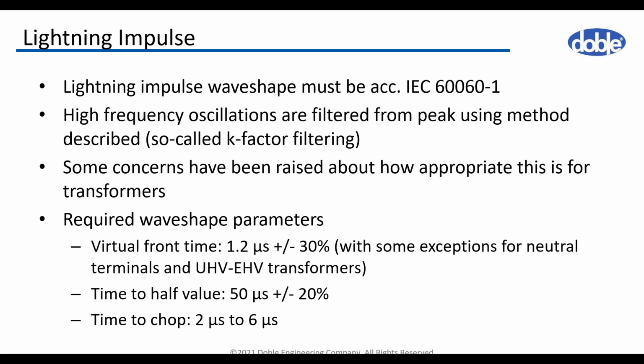The general definitions related to impulse tests and the requirements for the test circuit are drawn in IEC 60060 part 1. In some test circuits, oscillations may occur at the peak of the impulse, called overshoot, and if it is relatively high compared to the test voltage, then the testing is not that effective. IEC 60060 part 1 introduced a special factor, the K factor, in order to filter the high frequency noise and obtain the test voltage more accurately. But there are some concerns about how appropriate this K factor is for transformer testing.